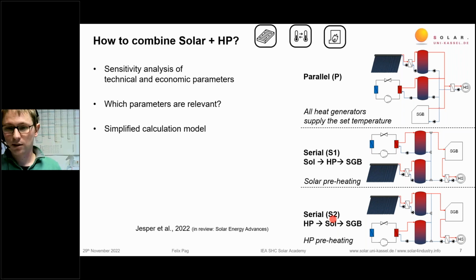As you can see on the right side, one basic idea was to have a look at different system designs. On the one hand, having solar collector field and heat pump completely in parallel, and then also two system designs where the solar collector field does a preheating and the heat pump ensures the set temperature, and vice versa, that the heat pump is doing the preheating and the solar collector field is designed to really reach the set temperature.